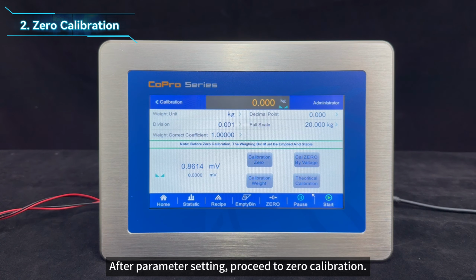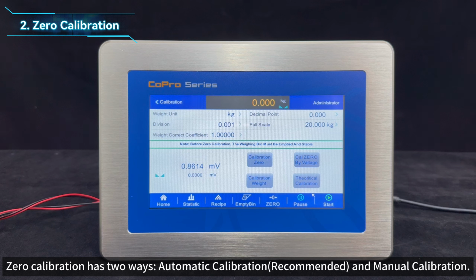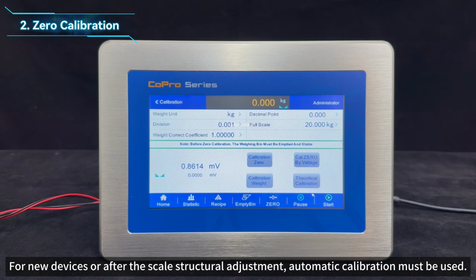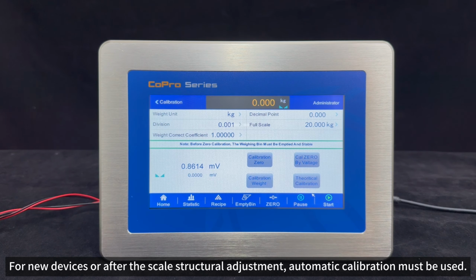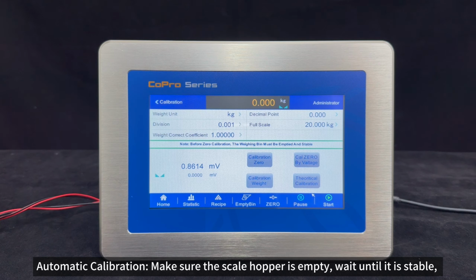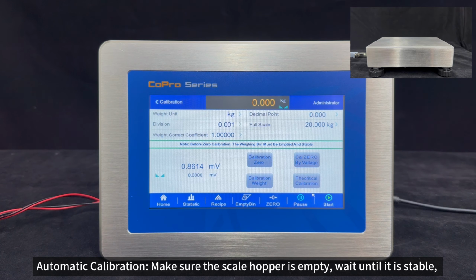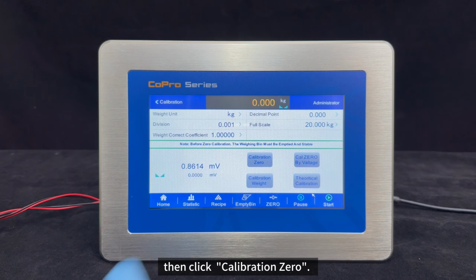After parameter setting, proceed to zero calibration. Zero calibration has two ways: automatic calibration and manual calibration. For new devices or after the scale structural adjustment, automatic calibration must be used. Automatic calibration. Make sure the scale hopper is empty. Wait until it is stable, then click Calibration Zero.